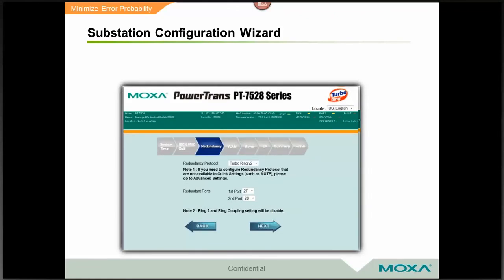According to the standard, you must use redundancy within 61850. So in this screen, you would choose a redundancy scheme. Here we've shown a turbo ring, a ring protocol that's very fast at recovering, down to about 12 milliseconds. Now you choose the ports using that redundancy, the primary and secondary port. Pretty simple. Here you fill out VLANs.